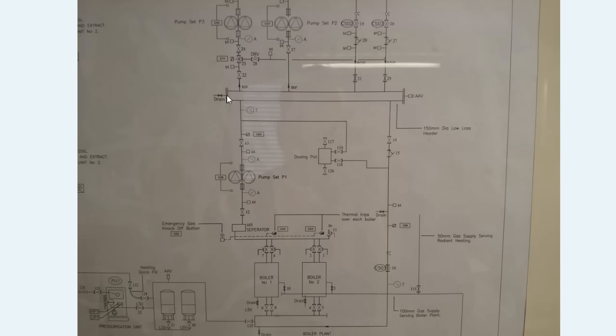You've also then got the secondary loops — we've got the pump set here and that's taken off, and you can see the multiple valve configurations there as well. And that's another secondary circuit coming off. Both of them are returning through this here, down into the common header. So that flow water will mix with this cooler return water and make its way back around to the boilers. And over here we've got the dosing loop as well.